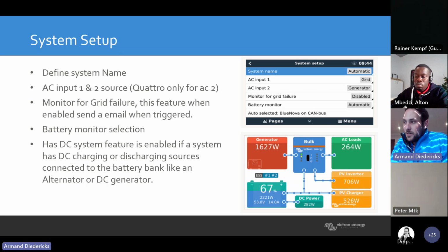Battery monitoring selection, you can go to battery monitoring selection. Most systems get SOC drift, what an SOC is, state of charge drift. If the battery monitoring is not set correctly and it goes to automatic, and it's not selected on BlueNova or SolarMD or on the BMS itself, it tends to get an SOC drift, and then it'll keep on switching the inverter on and off. So ensure your battery monitoring selection is set to the right parameter.